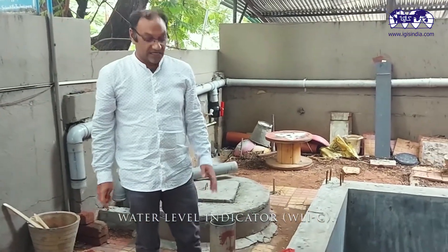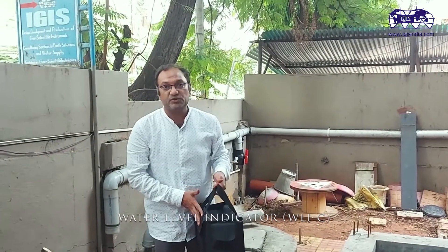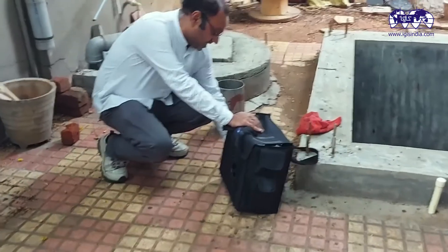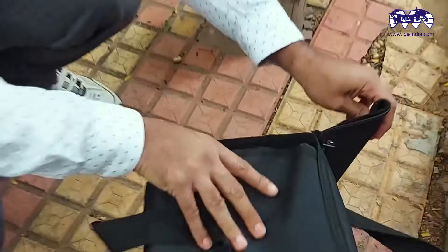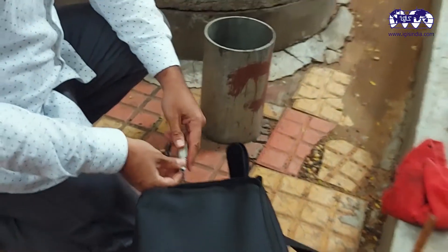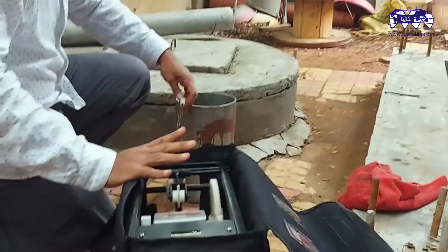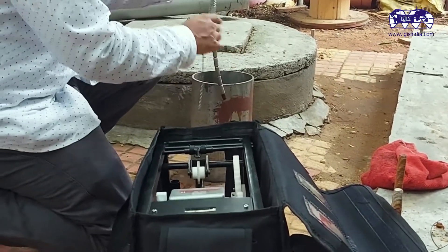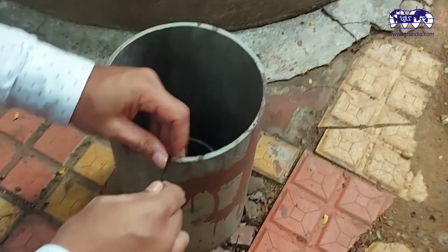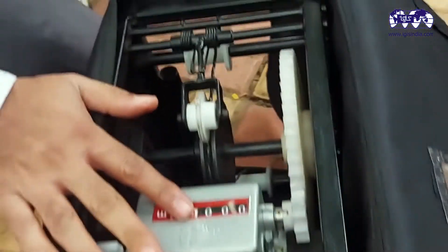Now let me explain how the equipment works. The unit is very simple to operate. As I mentioned, it need not be removed from the bag. Just position it at a place where you need to start your measurements. Unzip and pull out the cable and the sensor from the probe. Open the bag accordingly and drag the cable to set the position. To eliminate any initial length, drag it up and lower it down, then set it to zero. My measurement starts now — this length of the cable is eliminated.